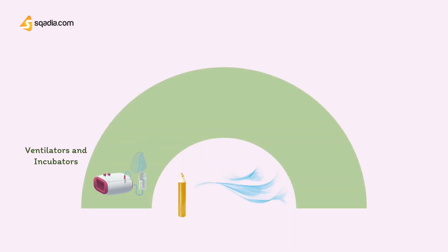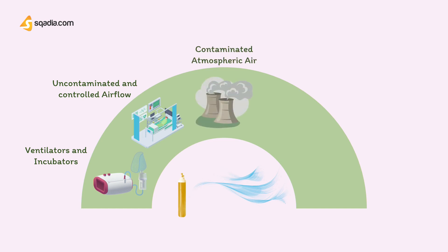The use of air is probably the most important for the vitality of critical patients. Air can be used in ventilators and incubators to provide uncontaminated and controlled air flows. It can also be used as a replacement for contaminated atmospheric air, as a carrier for volatile anesthetic agents, and as a power source for pneumatic equipment.